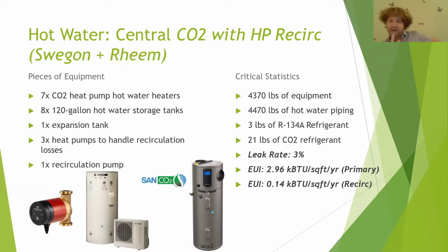The limitation with the CO2 heat pumps is that they don't want to see recirculation water, and when you use a central system, you need recirculation water—you can't just let the water get cold in those pipes, you need to move it around. They have smarter units now that actually learn from the building, so we can minimize the energy of the recirculation loop. There's a bunch of strategies for that, that's a whole presentation in itself.